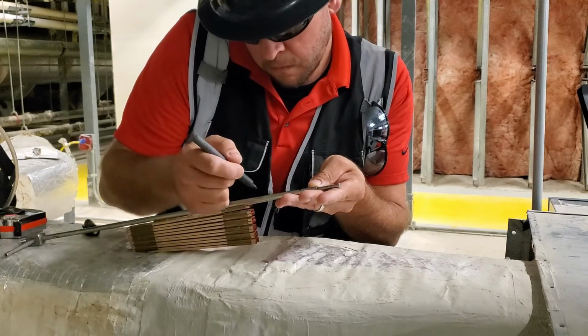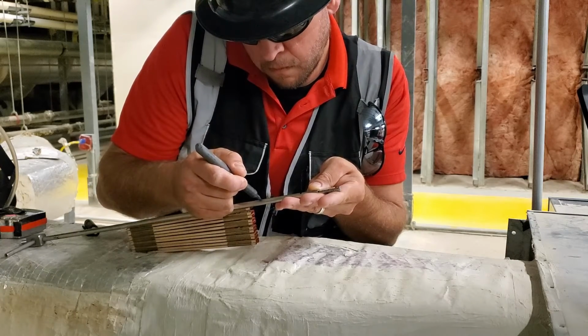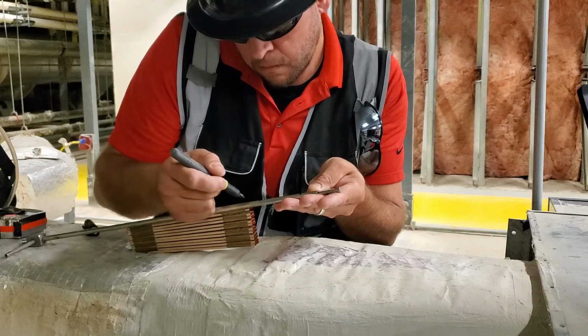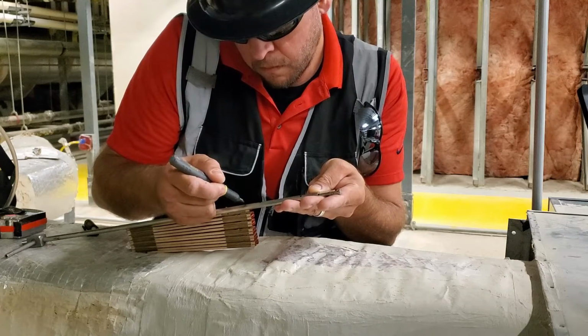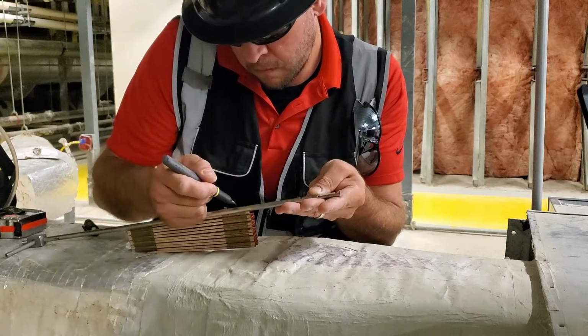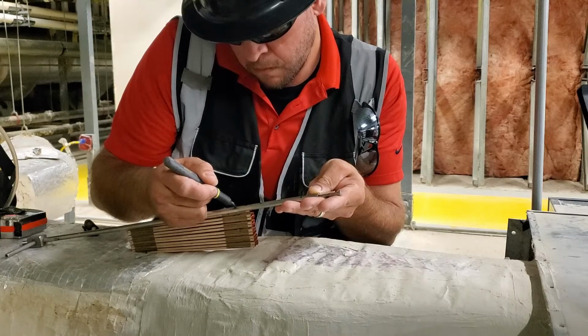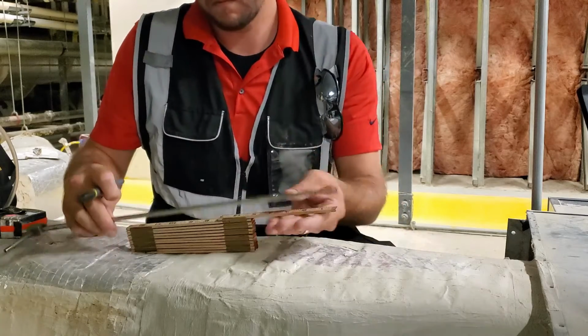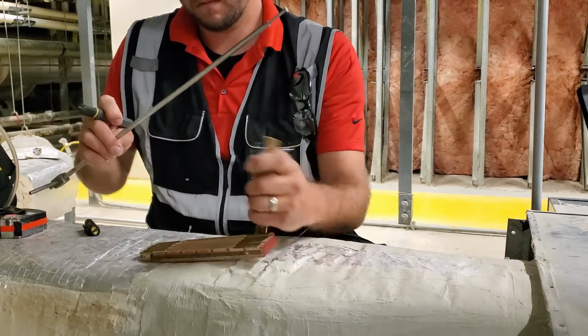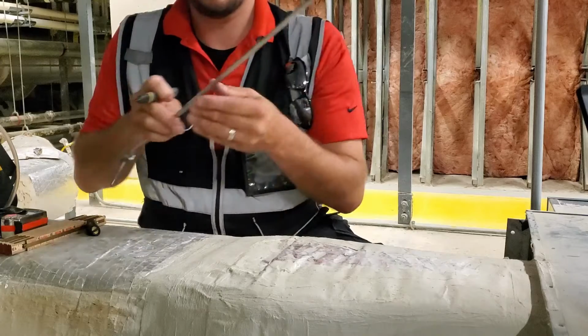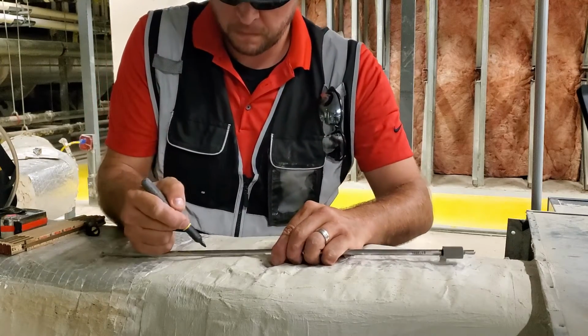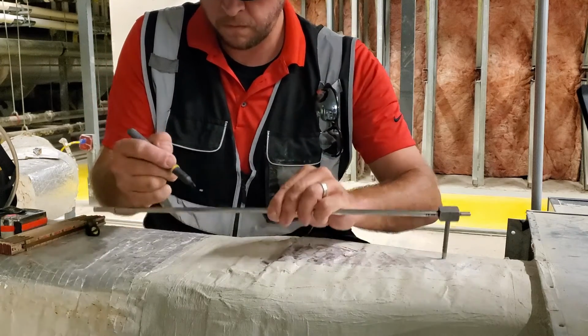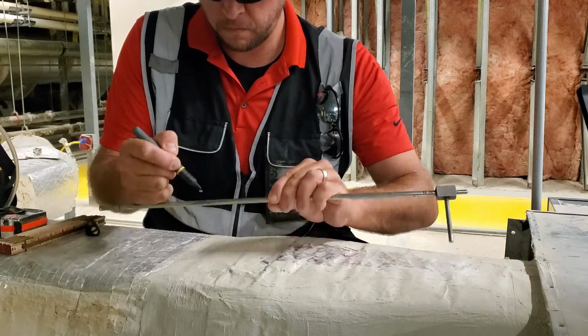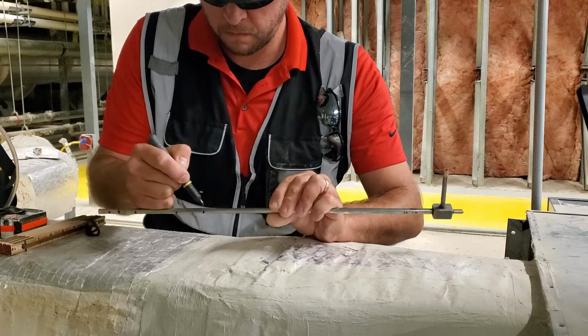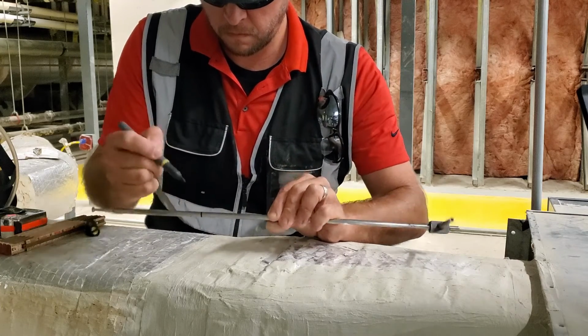And we measured the duct size. We know it's a 6-inch, so then we're going to mark our measurement locations on our airfoil based on that 6-inch duct reading. And so we're going to do 6 readings. We're going to do 2 holes, 6 readings. The holes will be 90 degrees apart. And then he's going to mark the airfoil, and then he's going to transfer those readings all the way around so that you can see it from every angle.